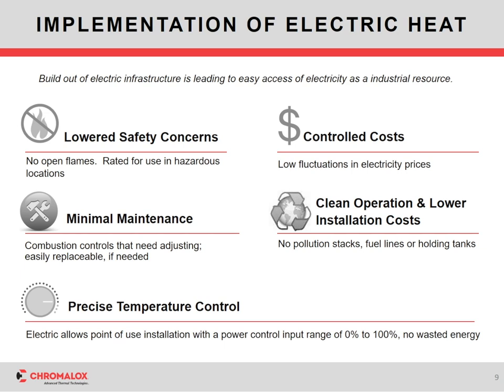And then really the big issue is, again, with electricity, you don't have to worry about the pollution stacks and the on-site maintenance. You have a very clean operation, a very low installation cost. And lastly, with electric heat, you're essentially converting 100% of that power into thermal energy. So you're able to very precisely control the temperatures and the operation of the equipment.